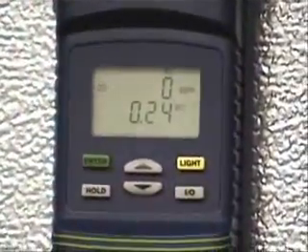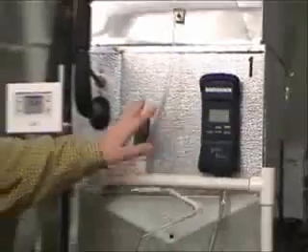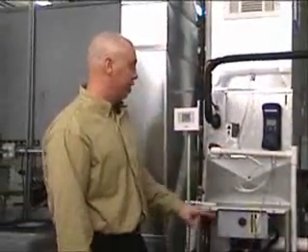That's pretty low — a pretty good number for heating. It's really low. But it's a false positive reading because that's not accurate — I'm not taking into consideration this coil or the filter.